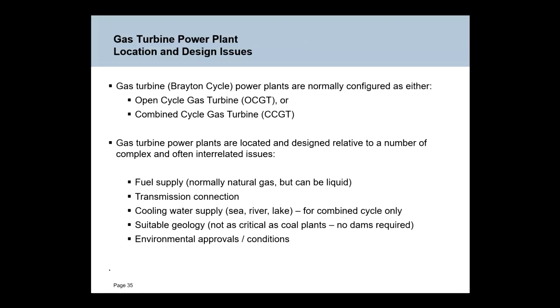Okay, so just like coal plants, if you want to build a gas turbine power plant, there are two types: open cycle, which is just the gas turbine with the exhaust gas exhausting to atmosphere, or combined cycle. We'll talk about what they are in a second. And just like the coal plants, a number of site selection issues. So you need fuel supply, normally natural gas, but gas turbines can also burn, for example, diesel or jet fuel. It's called a gas turbine not because it burns gas, but because once the fuel is burnt, you produce a hot gas. Okay. You need a transmission connection, same as coal plants. You need cooling water if you've got a combined cycle plant. You need the geology thing, but it's not as critical as for coal plants. And you need your environmental approvals to build a gas-fired power station.